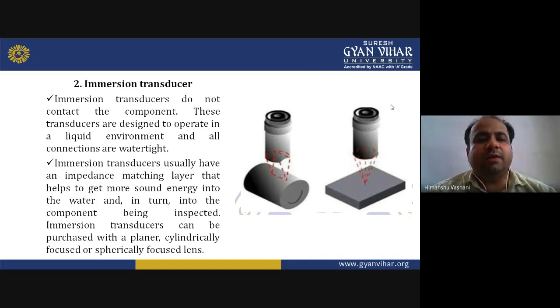Immersion transducers usually have an impedance matching layer that helps to get more sound energy into the water, and in turn into the component being inspected. That is the most important thing: the sound energy should go to the component through the water. Now, immersion transducers can be purchased with a planar, cylindrically focused or spherical focus lens. These are the kinds of available lenses. You can see on the right-hand side that a focus lens is used in the right image.